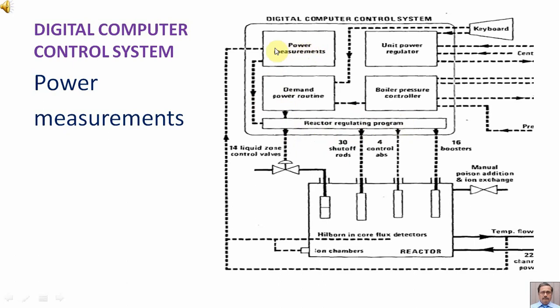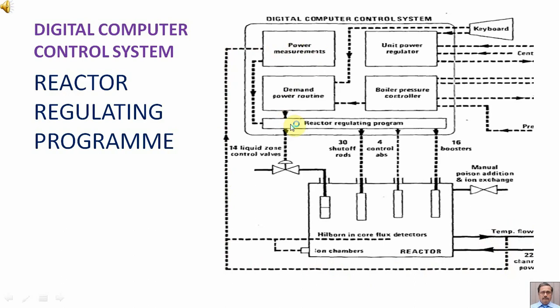The demand power routine is giving commands to the reactor regulating program. The power measurement unit is receiving signals from ion chambers, in-core flux detectors, and temperature and flow signals from the coolant reactor. The output of the reactor regulating program goes to the liquid zone control valves, the shutoff rods, the control absorbers, and the boosters.